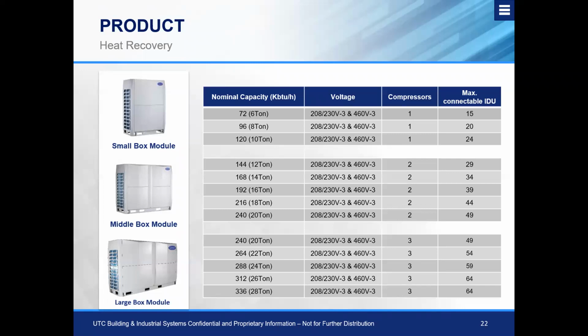Now, again, that is only the tonnage that will facilitate that many indoor units. It all depends on what tonnage you have for your maximum connectable indoor units that you can hook up to a Carrier VRF system. Now, of course, as we add more compressors and more coil surface area, we also gain better low ambient heating performance. So like I stated before with the derates, it ultimately depends on what configuration we have and also the connected capacity of indoor units versus outdoor unit tonnage.